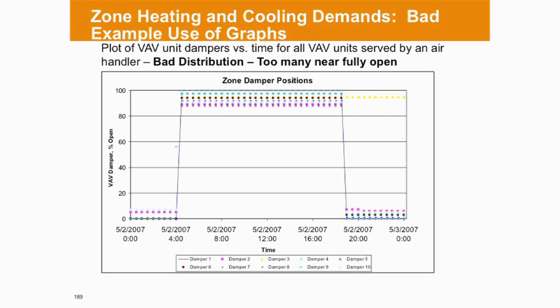So this chart shows almost all the zones are 90% or to 100% open. So that means the static pressure could be too low. So we have to increase static pressure a little bit so we can make the dampers close a little bit more because those zones might be starving for the airflow. And this chart shows that too many zones dampers are fully closed position.